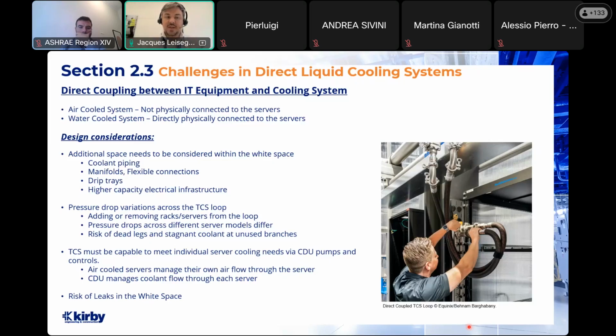So how do you manage that? If you are removing racks from your system, you have a risk of introducing dead legs into your system and stagnant coolant at unused branches. That can cause bacterial growth and contamination of your system.